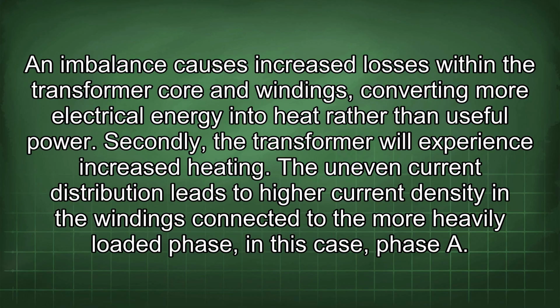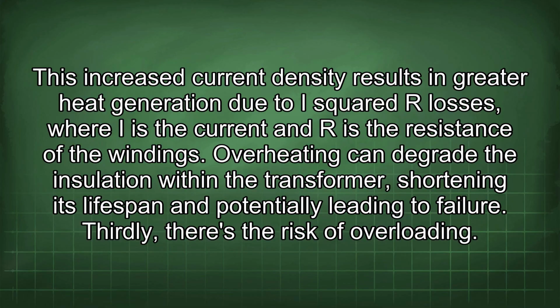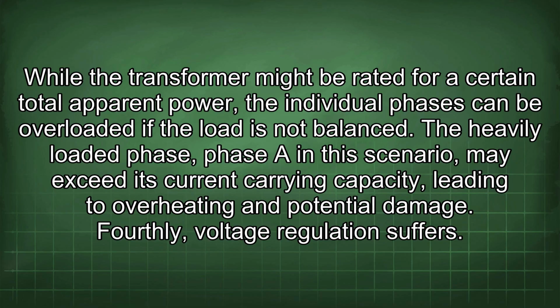Secondly, the transformer will experience increased heating. The uneven current distribution leads to high current density in the windings connected to the more heavily loaded phase, in this case, phase A. This increased current density results in greater heat generation due to I²R losses, where I is the current and R is the resistance of the windings. Overheating can degrade the insulation within the transformer, shortening its lifespan and potentially leading to failure. Thirdly, there's the risk of overloading. While the transformer might be rated for a certain total apparent power, the individual phases can be overloaded if the load is not balanced. The heavily loaded phase in this scenario may exceed its current carrying capacity, leading to overheating and potential damage.